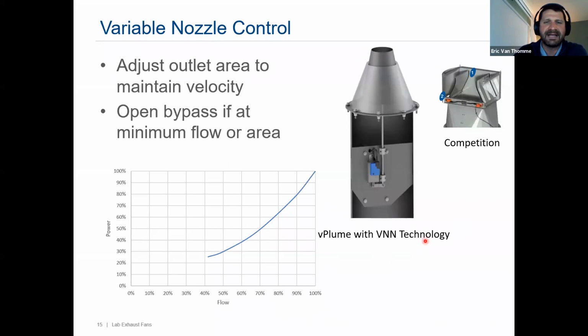And one thing I just wanted to highlight real briefly here is there's going to be, with any of these styles, some components that are potentially exposed to the weather and the elements. And all of our components are mounted actually down inside the nozzle and fan system itself, so they stay protected from the elements. Our competition has a similar design, but it's actually got these two damper blades. And as those modulate back and forth, they can be bound up, especially in climates where you have snow and ice to deal with.